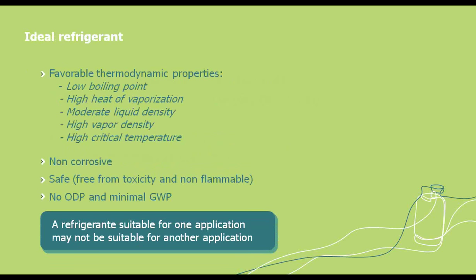There are several properties that make up what we would consider an ideal refrigerant. First, it would have a low boiling point — you want that boiling point to be a little bit lower than the temperature you're trying to achieve in your cabinet. A high heat of vaporization. You want it to be safe: free from toxicity and not flammable. You want no ozone depletion potential, mainly because that's outlawed and it's bad for the atmosphere. And a minimal GWP, the global warming potential of the gas, which impacts our atmosphere. Also, you need to pay attention to the application the refrigerant is being used in, as one suitable for one application may not be suitable for another.